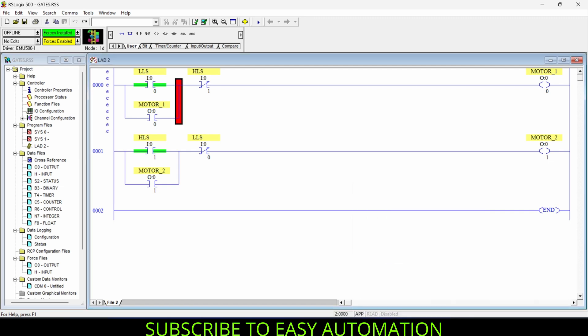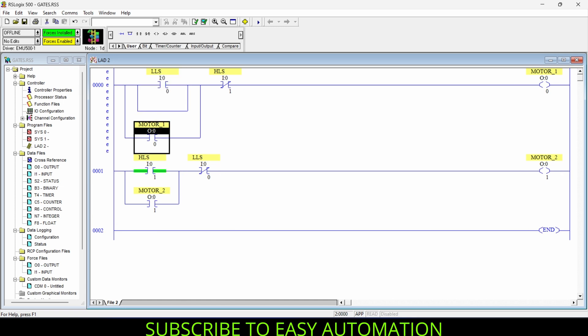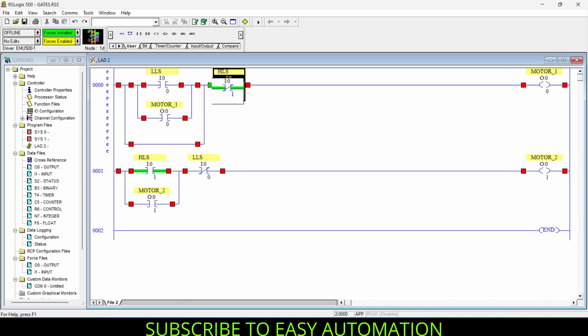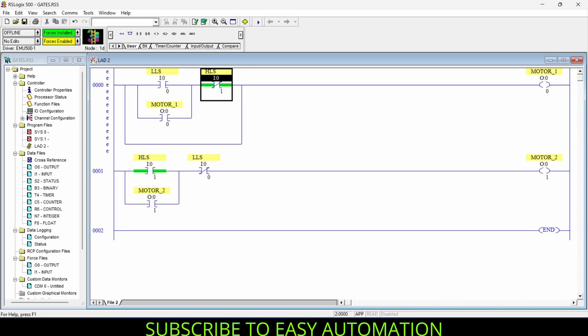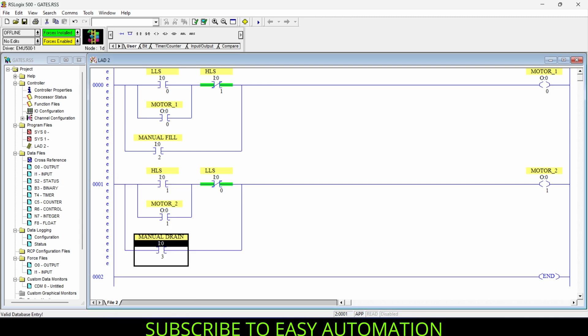To create the manual condition, we need a branch instruction with the Low Level Sensor and Motor holding inside it, and one additional NO contact for the branch. We copy this procedure for the second rung as well. For the new NO contact in rung one I've named it Manual Fill, and for rung two I've named it Manual Drain. The operator can toggle Manual Fill to fill the tank or toggle Manual Drain to drain the water.